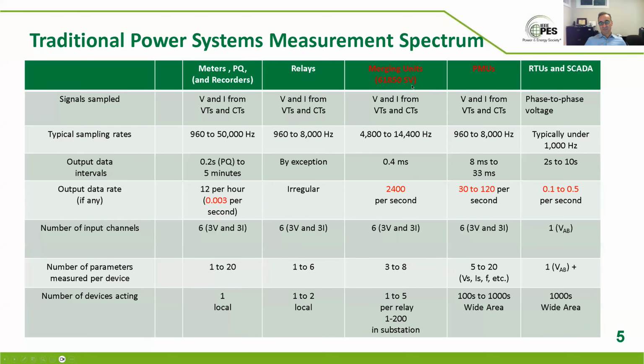You should always keep in mind, most of these electronic devices get their measurements from instrument transformers, and instrument transformers themselves may have bandwidth limitations, particularly capacitor VTs and even potential transformers. They have much narrower bandwidth. CTs have wider bandwidths depending on the load, burden, core size, things like that. Fine for current. But for voltage, a transmission PT usually doesn't have a bandwidth of more than 2 kilohertz. And CVTs are, of course, very narrow bandwidth. They're resonant tuned systems. So even at a few 100 hertz you see signals. It's not like you don't see any, but their accuracy is way, way, way off. It could be 10%, 20%. It could be 90% off, basically.